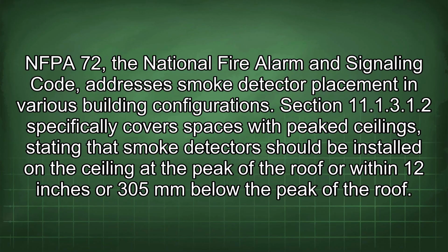NFPA 72, the National Fire Alarm and Signaling Code, addresses smoke detector placement in various building configurations. Section 11.1.3.1.2 specifically covers spaces with peak ceilings, stating that smoke detectors should be installed on the ceiling at the peak of the roof or within 12 inches or 305 mm below the peak of the roof.